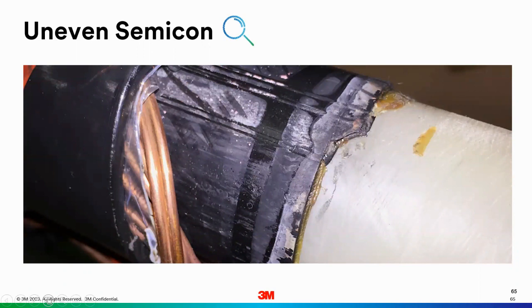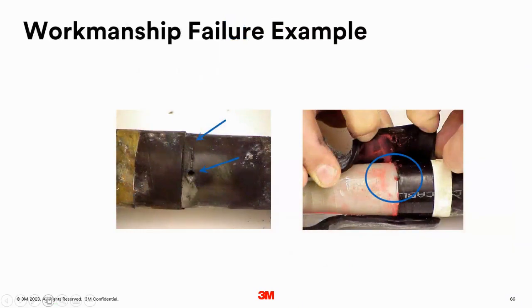This is an uneven semicon. You basically want this cut to be as square and straight as possible, and not jagged like this whatsoever. So this has to be the cleanest cut in your preparation. It's sometimes referred to as the money cut, because I think 90 some, I forget, 90 some percent of failures occur at this semicon. That's why they call it the money cut, because if you have a cable failure and your line's down, or part of your plant is down, you could be costing tens of thousands, hundreds of thousands, millions of dollars in some cases during a failure. So this one is important to be as straight as possible. And just workmanship failures.